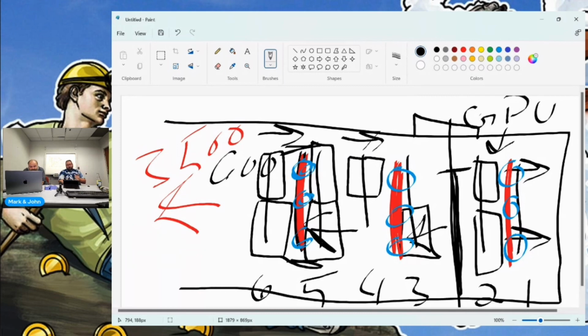So your fan RPMs drop from, say, 100 to 80. Our goal is to get fan speed down to 80 and have the exhaust fans doing the majority of the work, pulling the air through the machines and up and out. It's all about efficiency. These machines are fantastic about pushing air away from them, but we want the machines to focus more on hashing, not so much pushing all the power towards the fans.